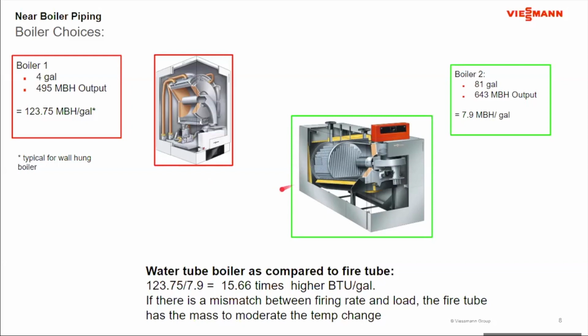With this boiler here, because I have a lot less firing rate input versus the number of gallons, the volume of this boiler allows the mass of the boiler to moderate the temperature change. What it really means is if there's a mismatch, this boiler's temperature changes much quicker than this boiler over here. It's a much more moderate change when there's a mismatch between the two, until the control circuit catches up with it. So we start to look at system design. That's something we have to consider when we look at the two styles of boilers.